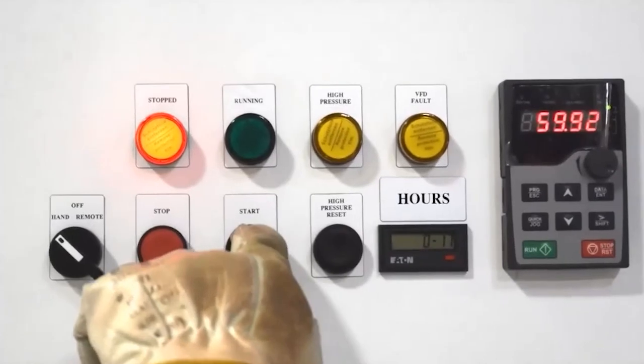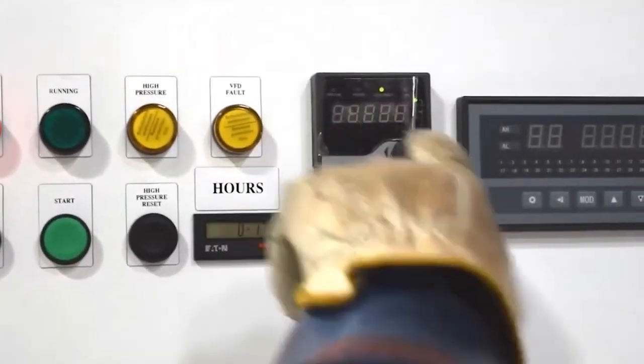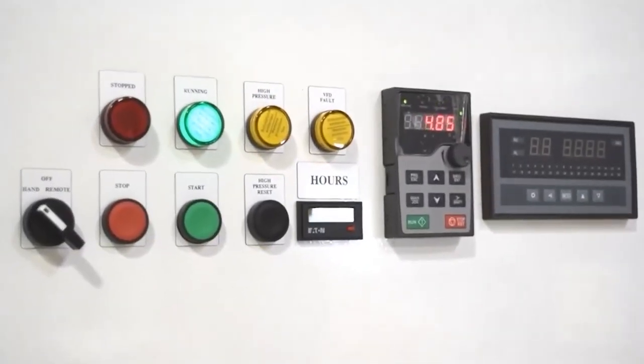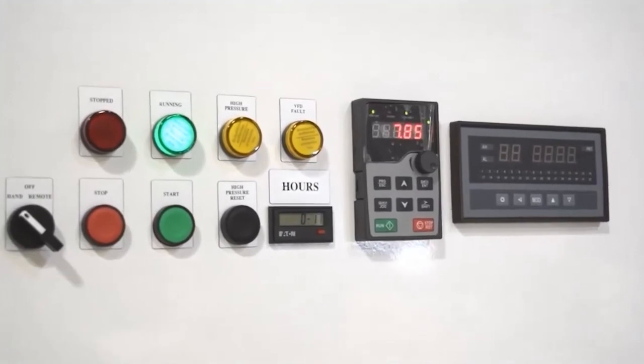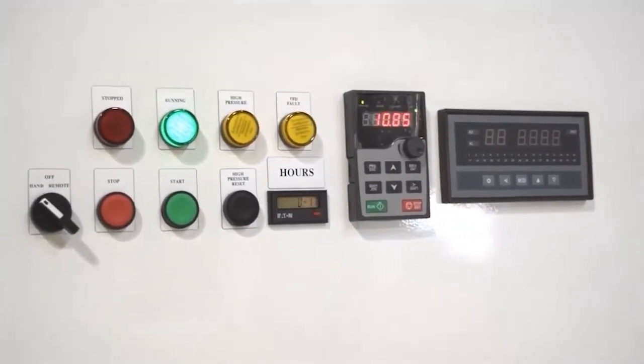To do that on this particular cabinet, I move the selector switch to the hand position and press the start button. There is a delay on this start because of our time delay relays. And once it begins to start, it's going to run up to about 60 hertz. And then I'm going to measure my output.